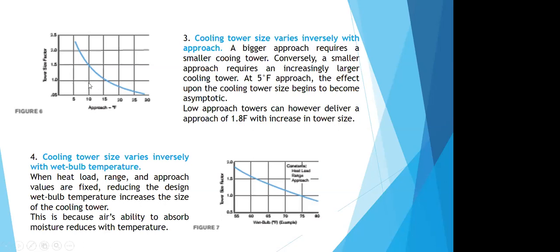If you reduce the approach by say 5 degree Fahrenheit, which is almost 1/3, 33%, your cooling tower size has gone up by almost 50%. And if you reduce the approach by say 10 degree Fahrenheit, which is like 66%, your cooling tower size has jumped to almost twice. So this is a key concept to understand, and it is important in low approach cooling towers when we look at the details.